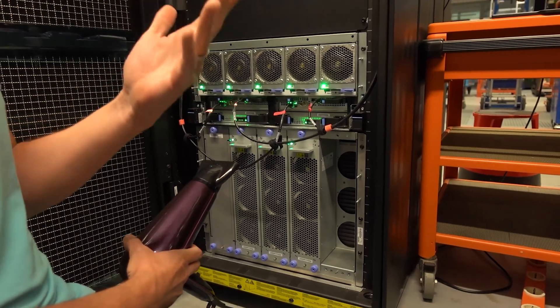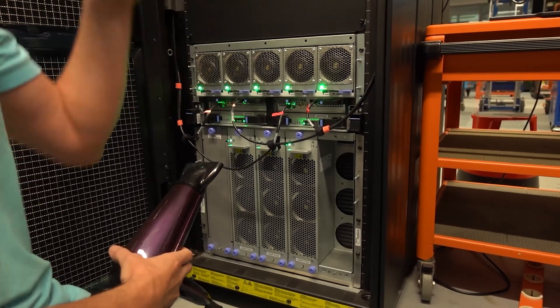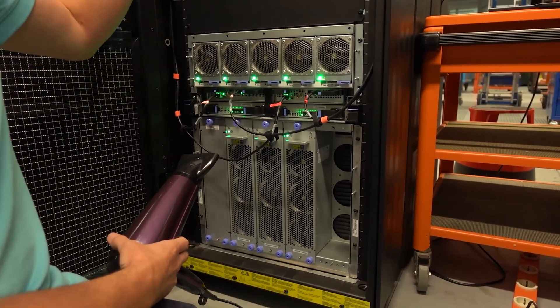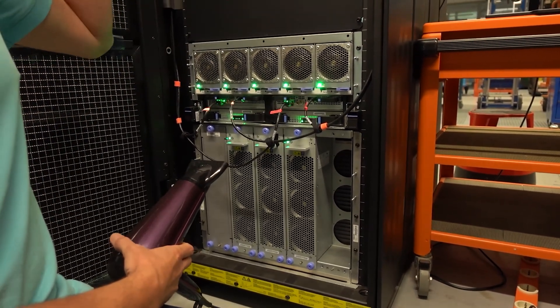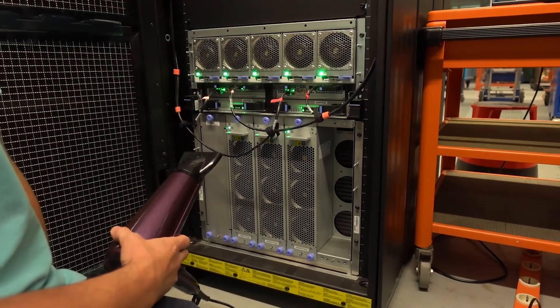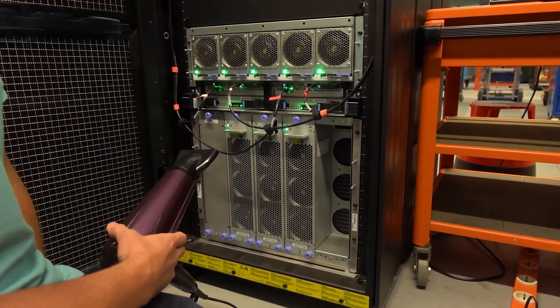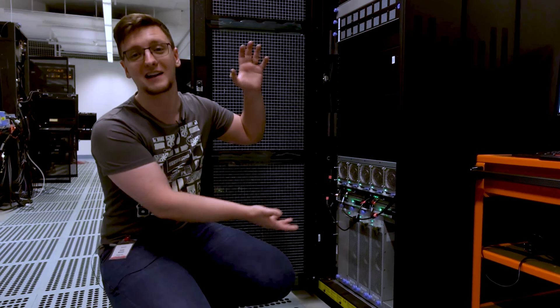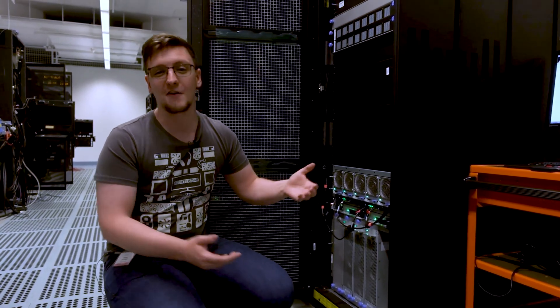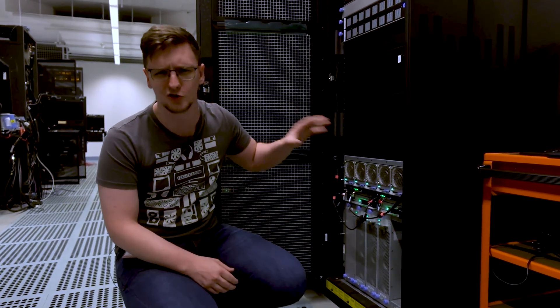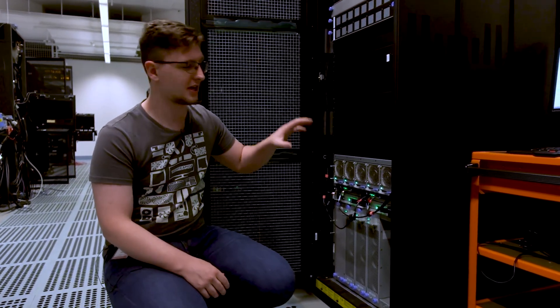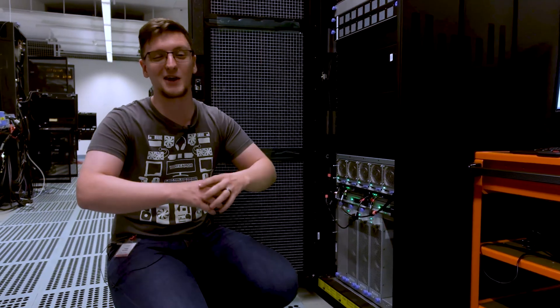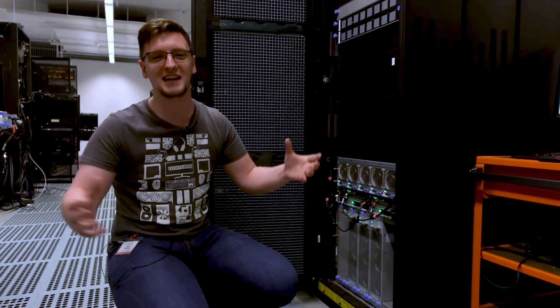So they use the hair dryer to trick the system into heating up to be able to show us that the energy advisor is actively telling the prospective owners that if you reduce the temperature in your data center by two degrees, you could save 120 watts just on this server alone. Imagine that scaled up to an entire data center and you can see where there might be some actual power savings to be had.